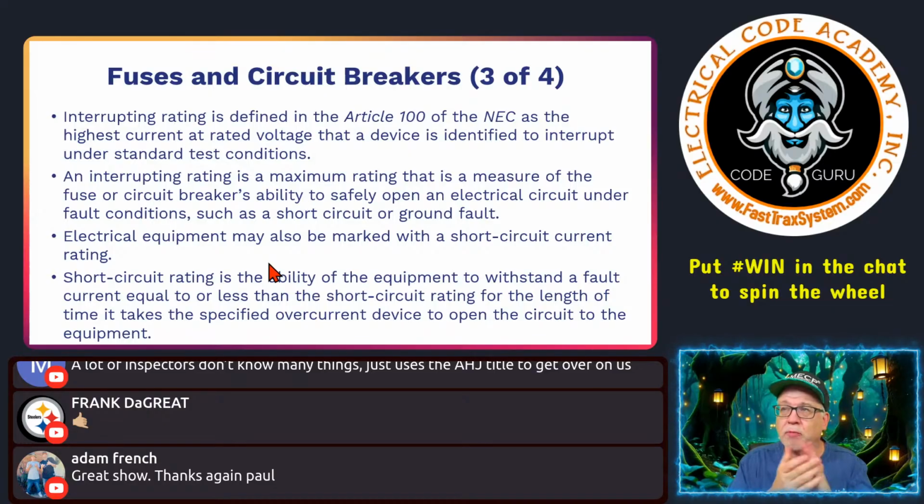Cooper Bussmann, which is owned by Eaton. They have a really simple calculator where you put in the length of conductor, and always use infinite bus because you don't know anything different. Measure the length, put in the type of conductors you have, whatever. It'll give you an idea of what it is down at the equipment. And remember, the longer your conductors from the source, the more the available fault current is going to go down as it gets further into the building.